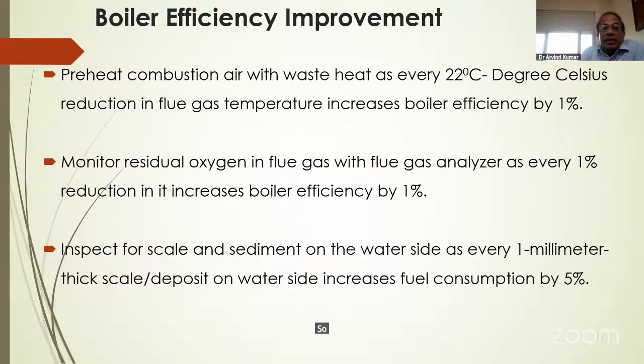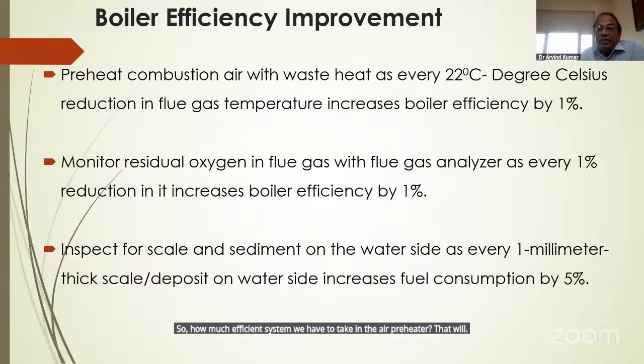Preheat combustion air with waste heat. For every 22 degrees Celsius reduction in flue gas temperature, boiler efficiency increases by 1%. If we use an air preheater, it preheats the air that is fed to the furnace, and if we increase the temperature by 22 degrees or a multiple of that, 1 to 2% energy is saved. So how efficient a system we take for the air preheater will be reflected over here.